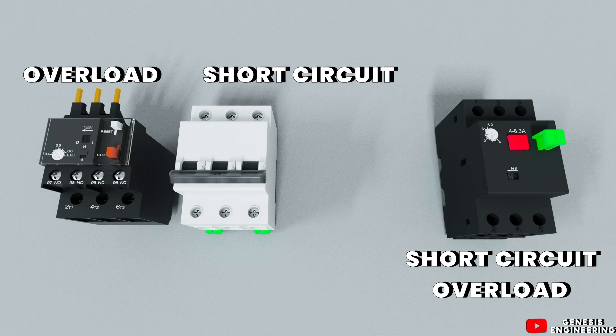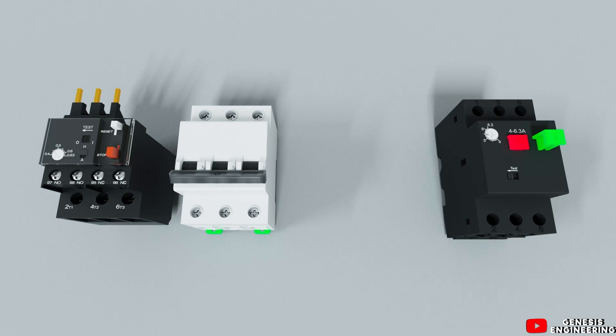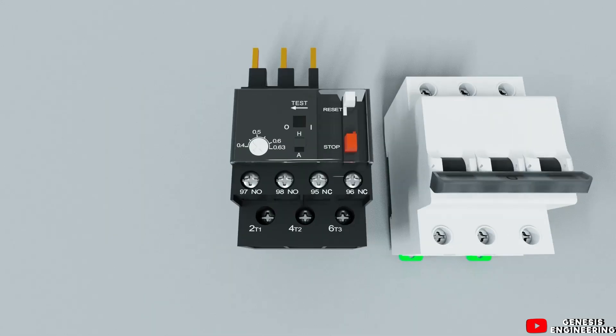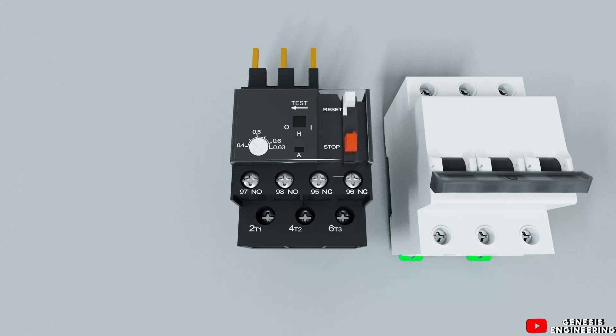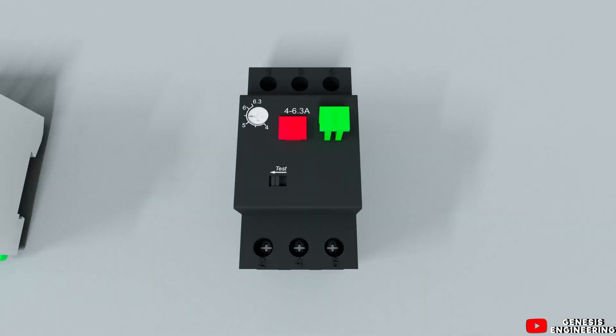With the motor circuit breaker we already have protection against both short circuit and overload. And, as with the thermal relay, on the motor circuit breaker you also have the option to adjust the current for thermal protection against overload.